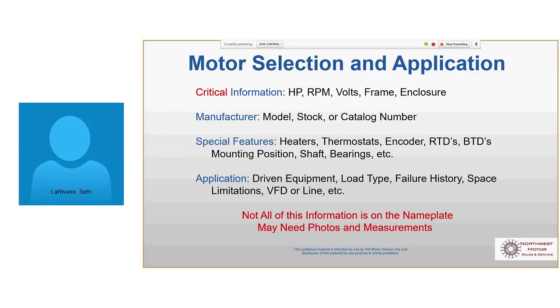And then we usually want to know if there's anything unusual about the driven equipment. Is it a pump or a fan or a conveyor? Because that tells me what kind of load it's on. Is it on a VFD or is it across the line? Is there any unusual failure history to this equipment? I mean, are you replacing this motor regularly? Then we got to look at upsizing the horsepower or why it's failing and kind of come to a more intelligent solution than just replace.